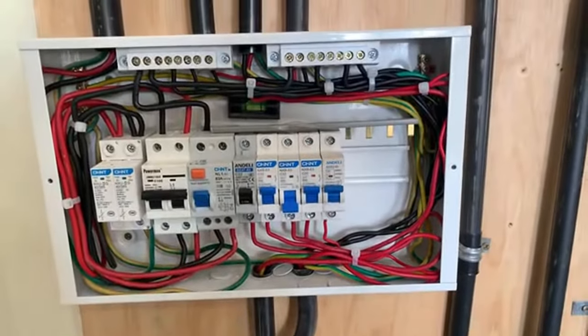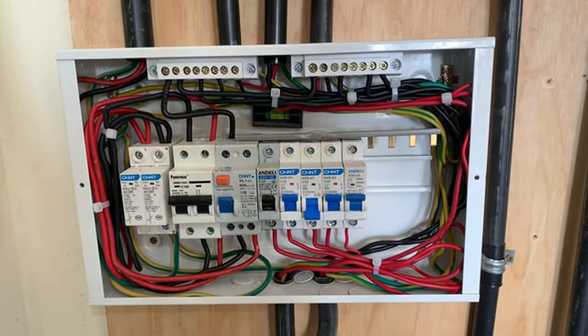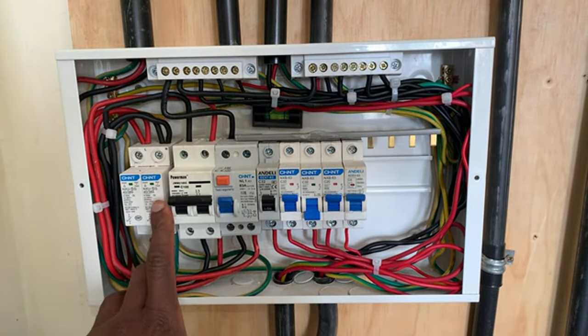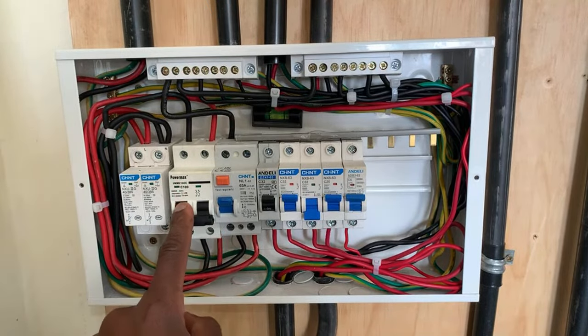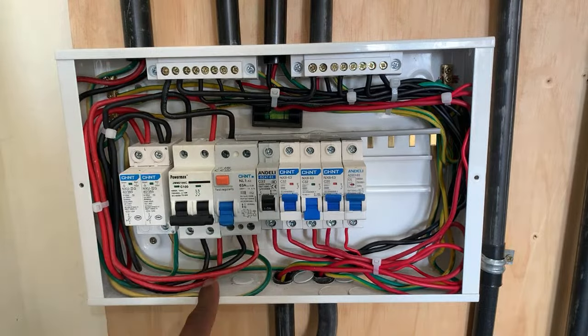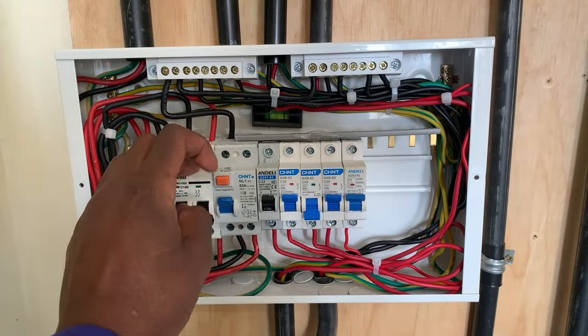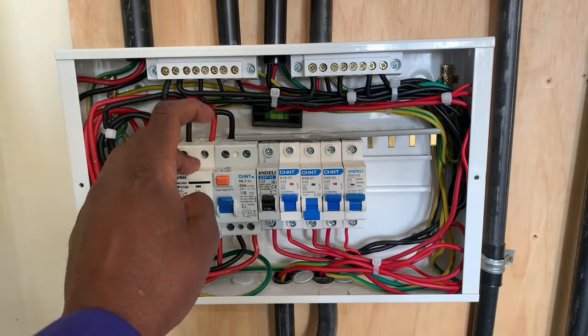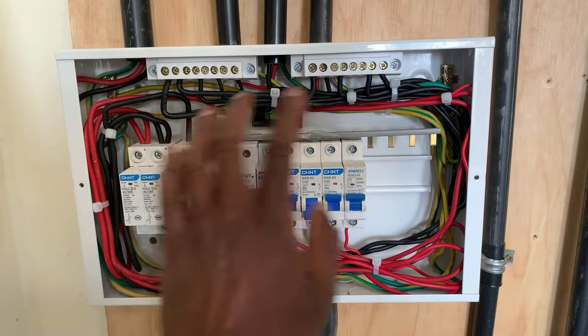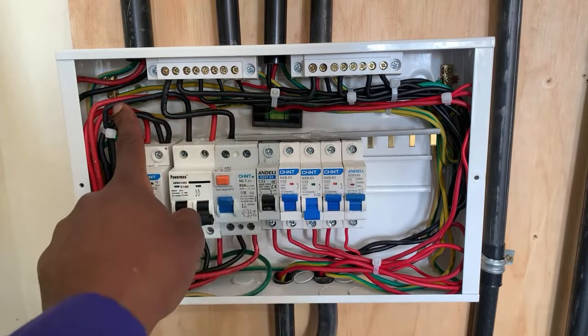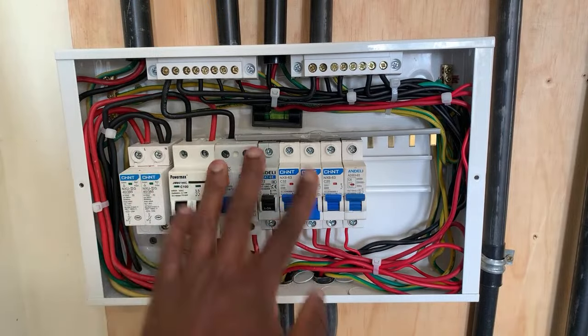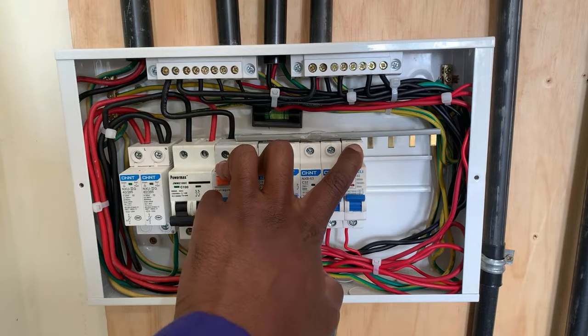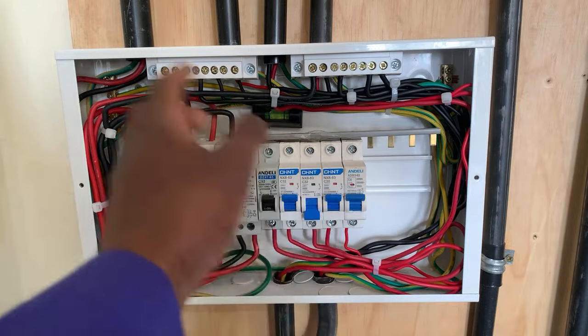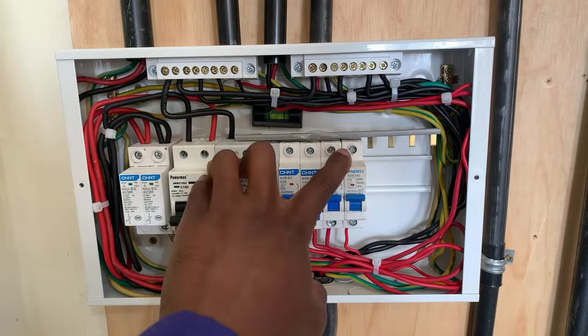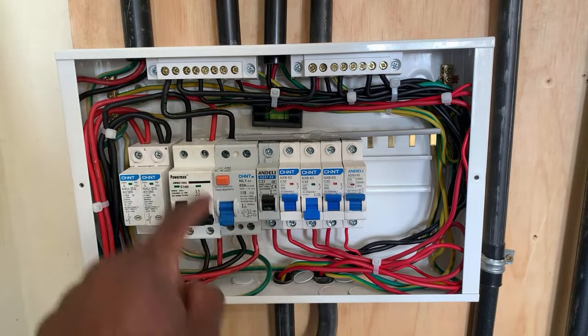So this is basically a consumer unit in a single phase domestic wiring. This is our surge diverter. This is our double pole or DPMCB. This is now what is very important in this circuit. This is our RCCB or the RCD. It protects the circuits against a phase to earth leakage. So if someone is receiving an electric shock, if there is current flowing from the phase to the earth connection, then you will have this RCCB trip.